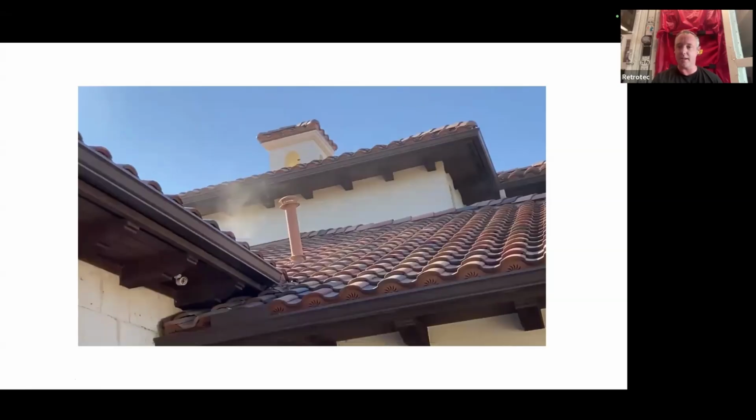So even though this attic got spray foamed, it was still having a lot of humidity problems afterwards because it was still super leaky at the end of the day. So that's what they missed.